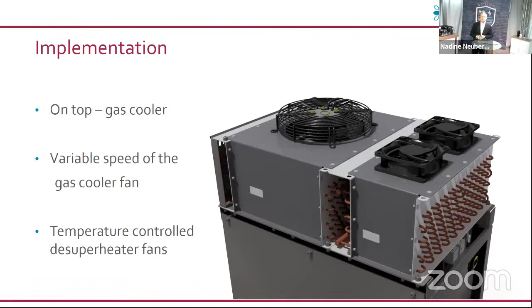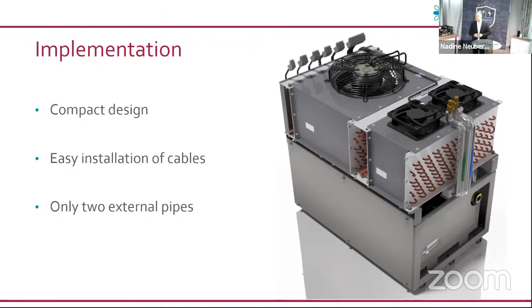Also, this unit has a very compact design. This compact design has the advantage that we could install it in very small spaces, which was also a guideline in this project. The electrical installation is quite easy because all the connection cables have plugs. So you have to put the unit in the slide, connect the plugs, and push it completely in. After this, you only have to connect 2 external pipes at the front of the desuperheater.